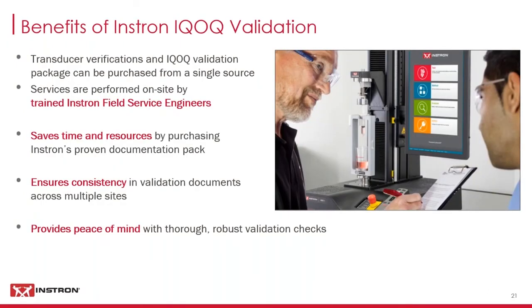For medical device and pharmaceutical companies, software validation is critical for compliance with regulatory standards. There are several benefits to purchasing IQOQ validation through Instron. Offering both transducer verifications as well as IQOQ validations allows Instron's customers to purchase all services from a single source. Calibration and IQOQ services are performed at your site by trained Instron field service engineers. The IQOQ validation and transducer verifications, which are also sometimes referred to as transducer calibrations, work together to ensure software works as intended and yields accurate, reliable results.